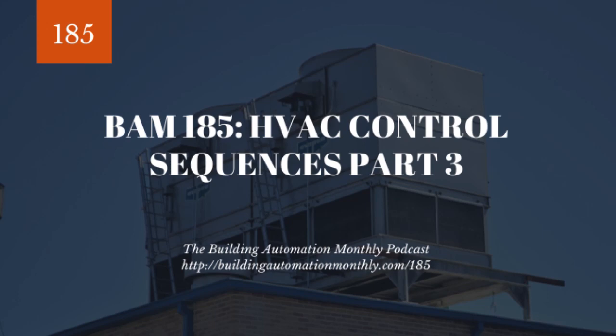So for those of you who are troubleshooting or programming, you really got to have your airflow down, because if you don't have that, you cannot change the environmental quality of a space. I really want that to sink in. I see a lot of folks who will spend a lot of time troubleshooting temperature and humidity and not look at airflow and be like, hey, I can't control the space. Well, the space is designed for 1,000 CFM and you're giving it 500 CFM. Well, of course you're not going to control the space. It's not going to happen.